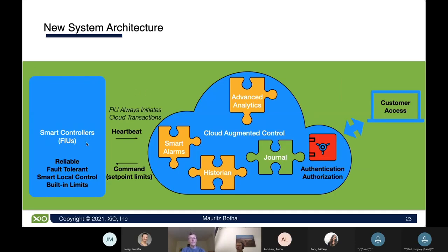The new system architecture used smart controllers that sent a heartbeat to what we call cloud augmented control. The difference is the smart controllers are reliable and fault tolerant, meaning they work in the presence or absence of the cloud. They will still perform their task: if a tank level drops too low, they start the pump; if it gets to full, they stop it.